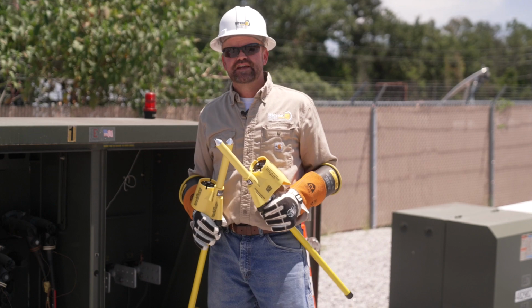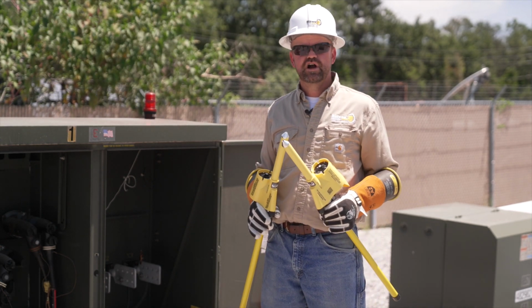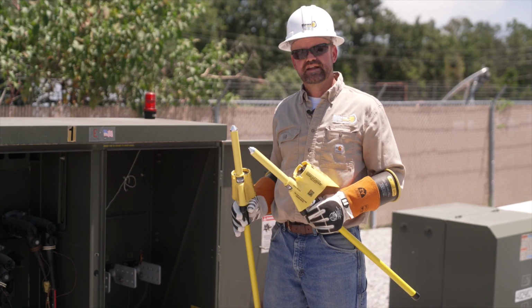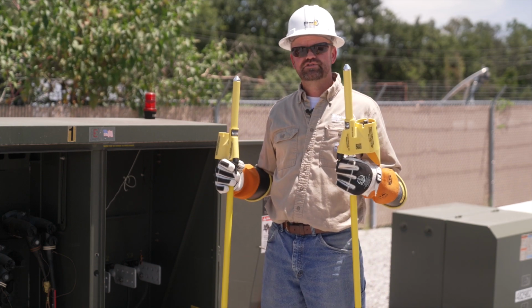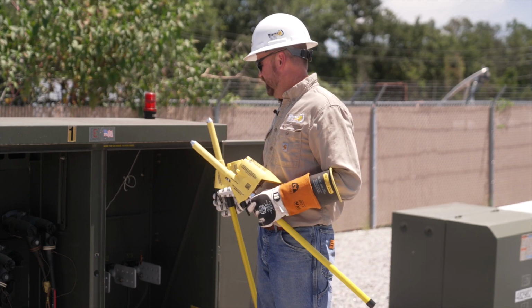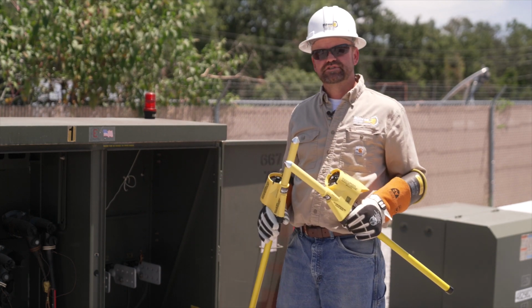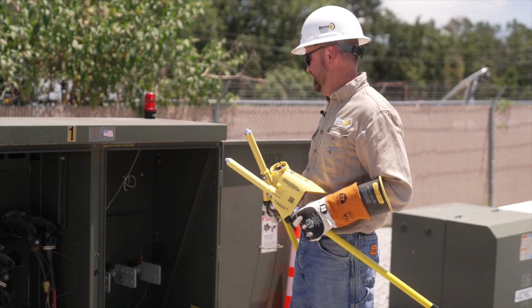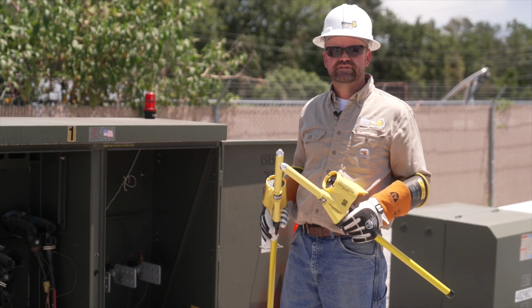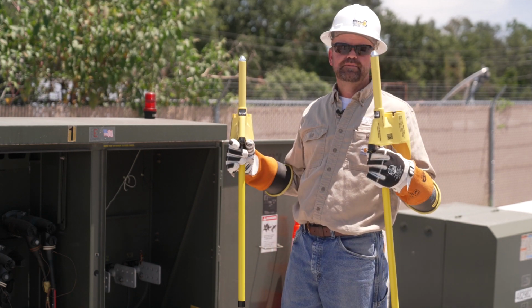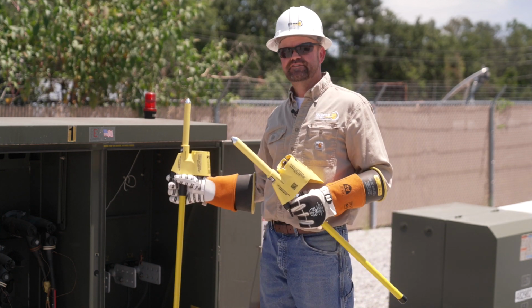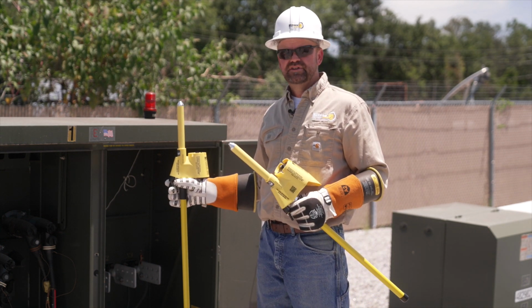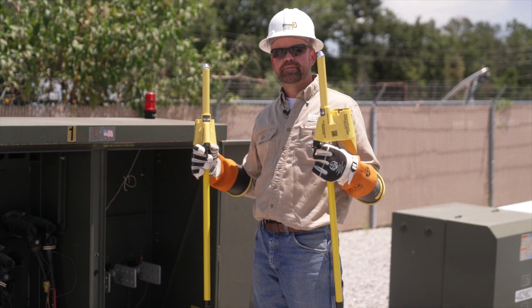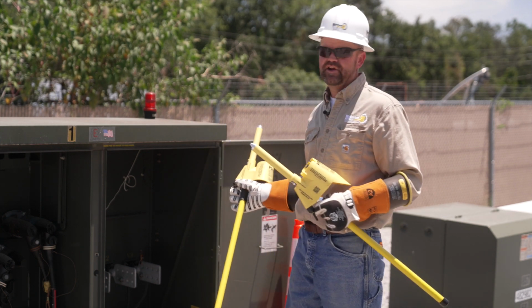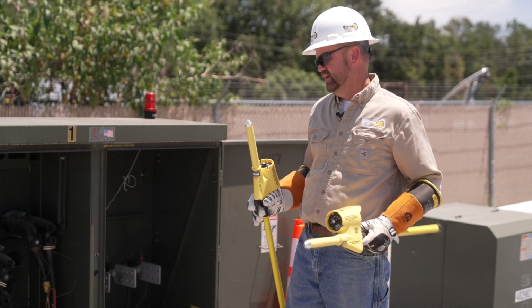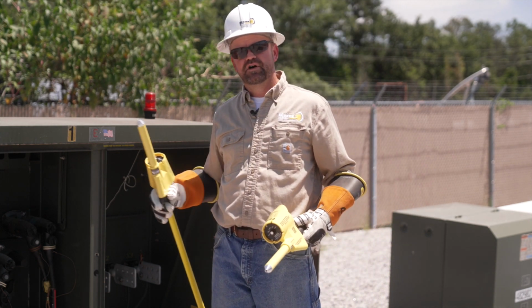If a customer has a phase rotation device, in other words, a clockwise or counterclockwise tool for secondaries, you can actually replace that tool using this device. In other words, if a customer uses that device, the clockwise or counterclockwise device on this situation, and it tells them this is counterclockwise, from that point forward, the PD800W, if your sequence is from right to left, is considered counterclockwise. So you would essentially replace that tool using a primary rated tool versus a secondary rated tool in this situation. Now I can perform that same thing on my primary.